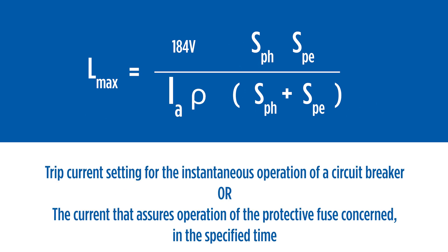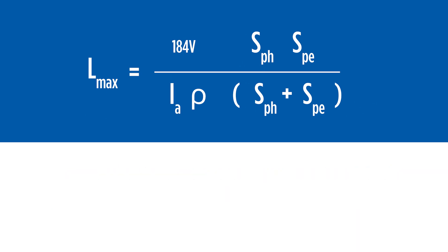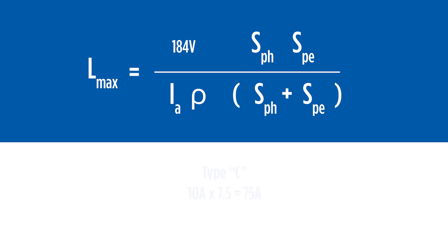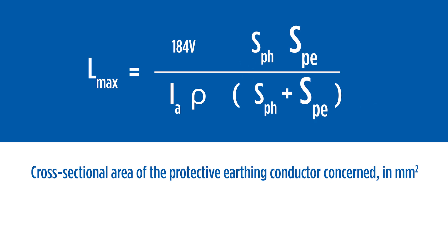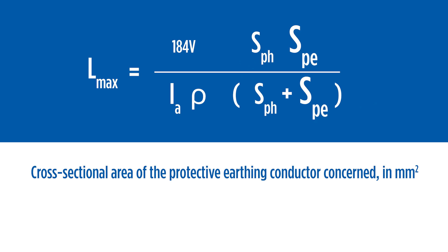IA represents the protection device's current value for instantaneous tripping. For example, a 10-amp C-type circuit breaker requires seven and a half times its rated value for instantaneous tripping. The final consideration is the cross-sectional area in millimetre squared of the phase and protective earth conductors.